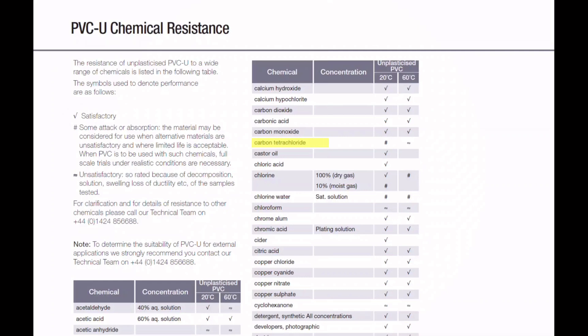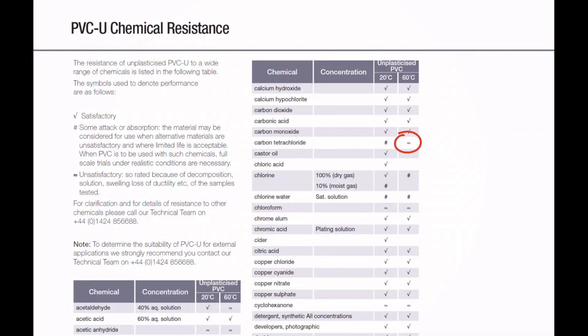However, looking at something like carbon tetrachloride — used as a cleansing agent in the dry cleaning industry — at 20°C it's rated with a hash mark, which according to the key means 'some attack or absorption; the material may be considered for use when alternative materials are unsatisfactory and where limited life is acceptable; when PVC is to be used with such chemicals, full-scale trials under realistic conditions are necessary.' So that should trigger you to think about an alternative material. At 60°C the chemical is rated as unsatisfactory — rated because of decomposition, solution, swelling, loss of ductility etc. of the samples tested. So clearly that would not be an acceptable application of PVC-U containment if it's likely to come into contact with that chemical at that temperature.